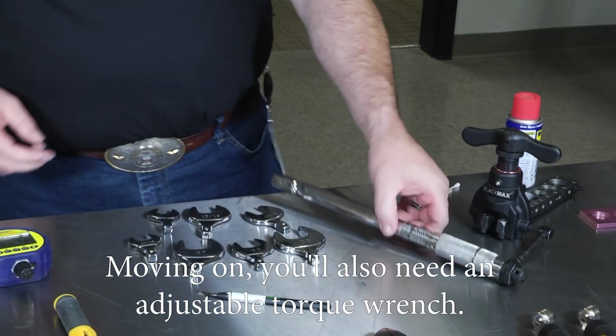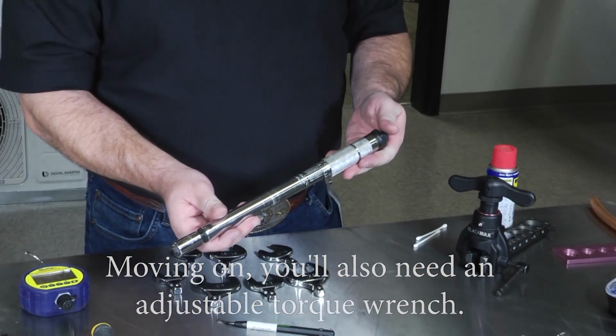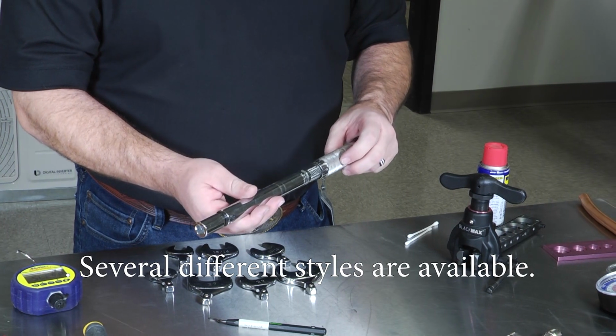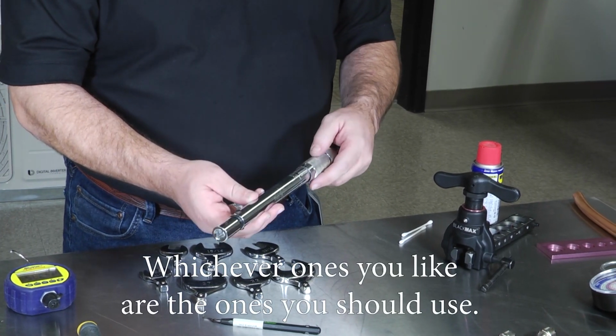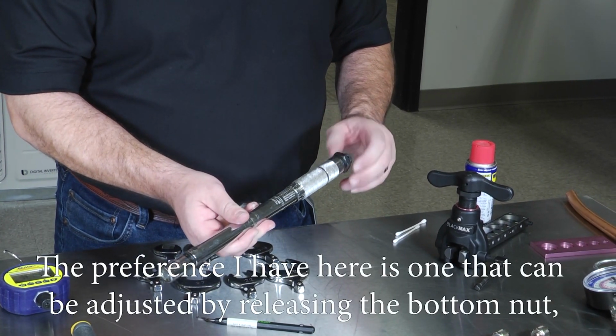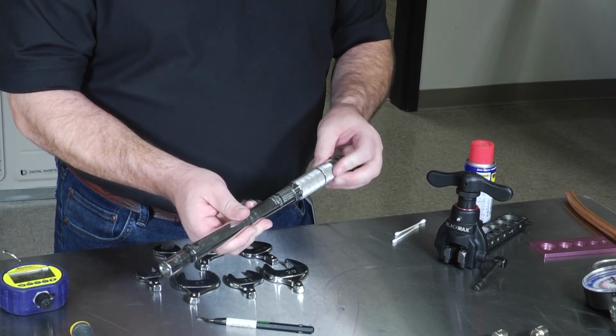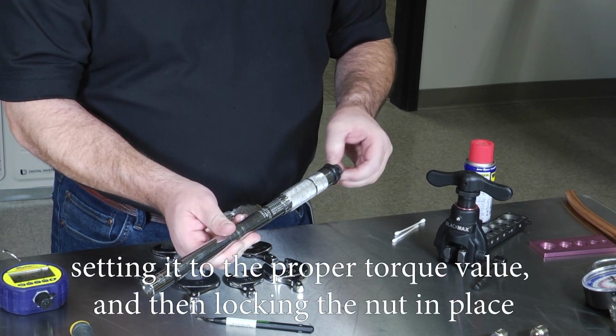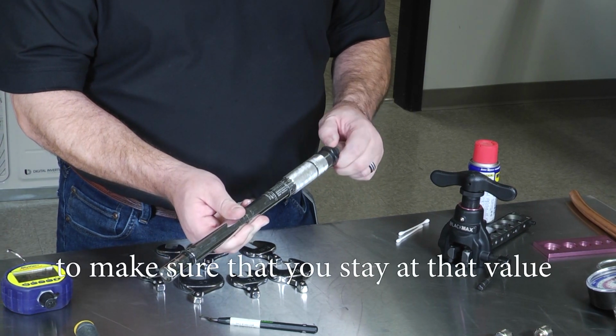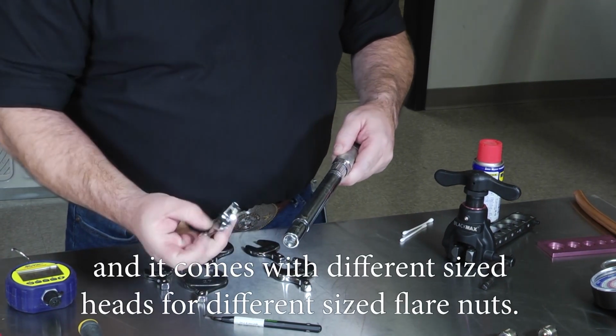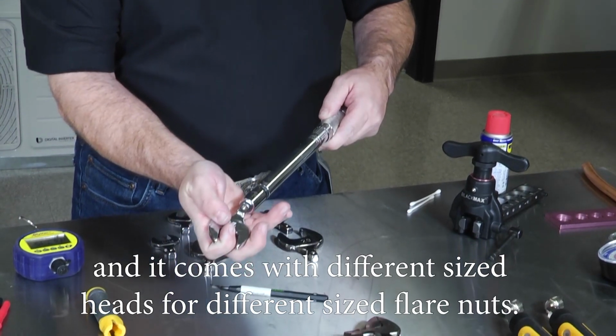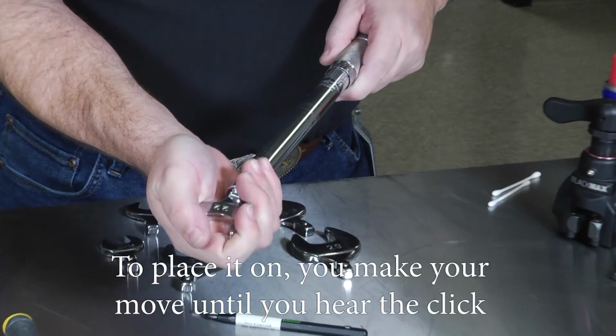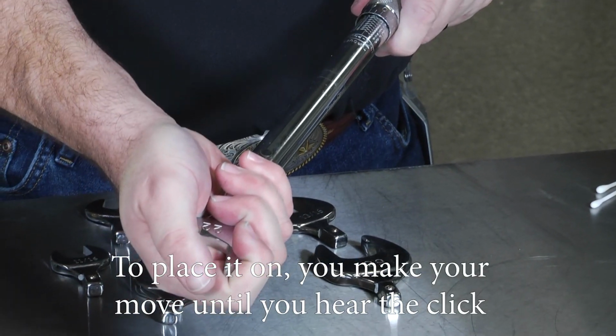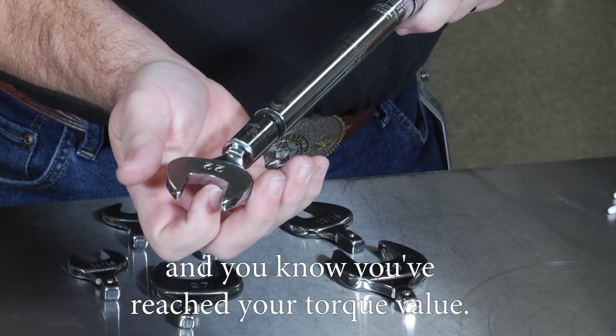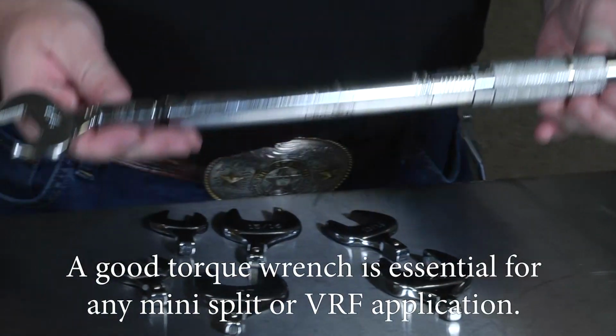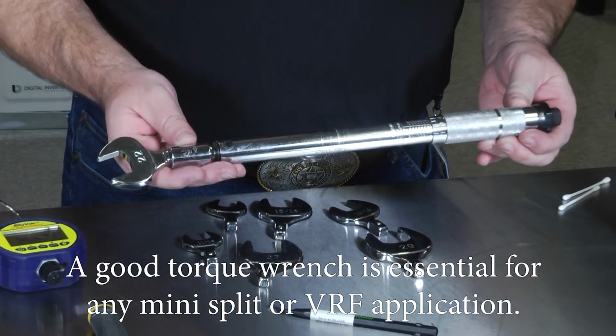Moving on, you'll also need an adjustable torque wrench. Several different styles are available. Whichever ones you like are the ones you should use. The preference I have here is one that can be adjusted by releasing the bottom nut, setting it to the proper torque value, and then locking the nut in place to make sure that you stay at that value. And it comes with different size heads for different size flare nuts. You place it on and make your move until you hear the click, and you know you've reached your torque value. A good torque wrench is essential for any mini split or VRF application.